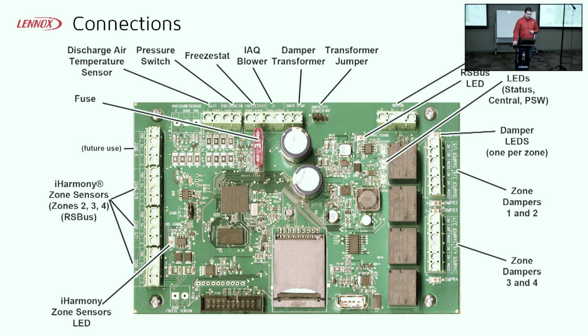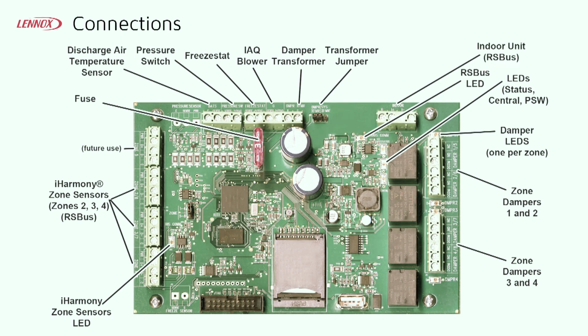So something else that's good to know about these is you have these damper lights. I don't know if you can see that on that picture there. They're kind of reverse logic, so they're going to light up when that damper is closed. That's something else that can cause some confusion on these. I've experienced that going over the phone with guys, where the thought is, oh man, the light's coming on telling it to open up, but it's closing off. And I tell them, no, it's the reverse.